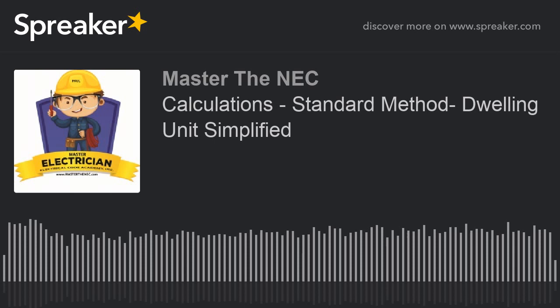Next, we're going to electric clothes dryers. All right, again, a one-family dwelling or individual dwelling units of a multifamily building can use this process. It doesn't change. All right, so we're dealing with the clothes dryer for that individual unit. Now, what does the code say about clothes dryers? It says the load for household electric clothes dryers in a dwelling unit shall be either 5,000 watts, and of course we can say it's VA, or the nameplate rating, whichever is larger.